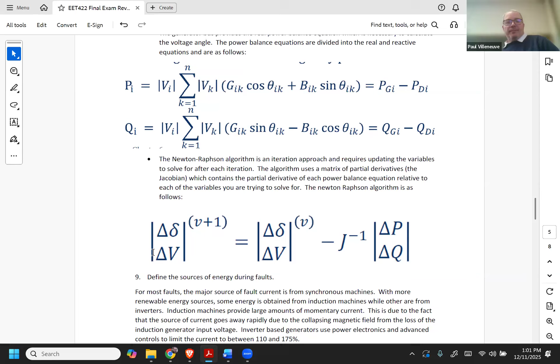Then we talked about the different time periods in a generator when it experiences a fault, and how that current changes. It has to change because you have different sources of energy: energy that happens for a subtransient time, energy for a transient time, and energy for steady state. Each of those is modeled as a decaying exponential, just like in any first-order electric circuit, an L and R circuit with a time constant. We do the same thing here, but add it all up into one equation so we can model what happens to the energy over the course of a fault.